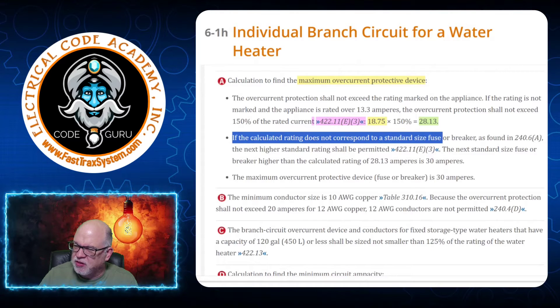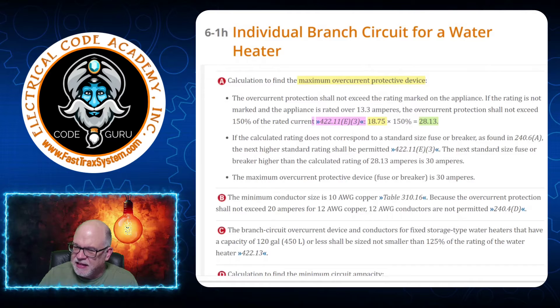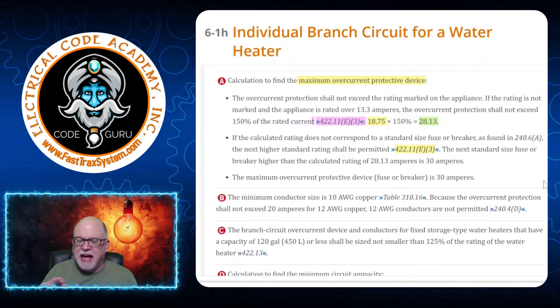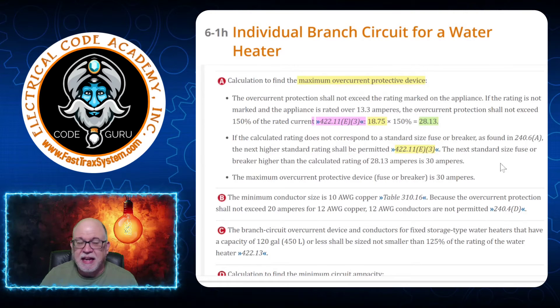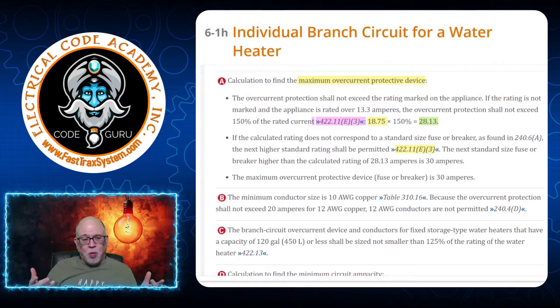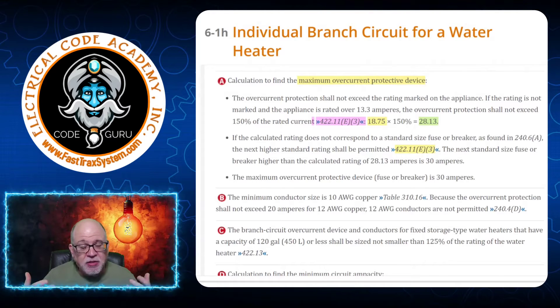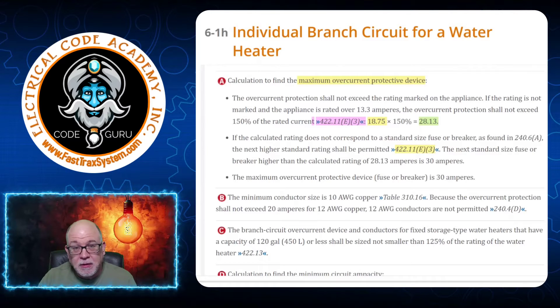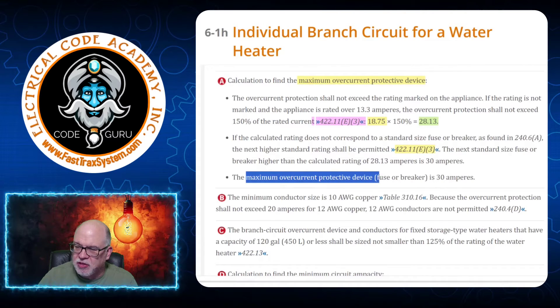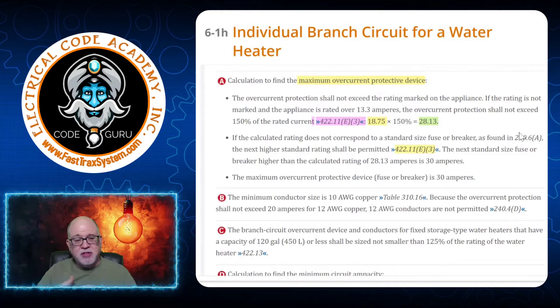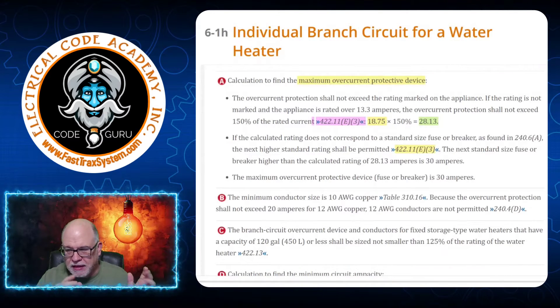The permission to round up to the next standard size comes from 422.11(E)(3), which we just read. The next standard size is 30 amps. So if you're asked what is the maximum size overcurrent protective device for a 4,500-watt, 240-volt water heater, the answer is: the maximum overcurrent protection — fuse or circuit breaker — is 30 amperes. That's the maximum rule.